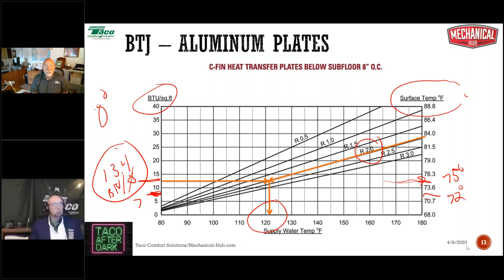So I think where John was going with that is he was asking what's the one thing that tells the heating system when to stop giving heat. And of course, it's the room temperature and the thermostat that's in the room, right? So I always looked at it like a triangle. At the top, we have room set point temperature. Down on one end of the pyramid, we have the BTUs per square foot. And out on the other side, we have what the surface temperature is. So surface temperature is tied to the BTUs per square foot, is tied to the set point temperature.